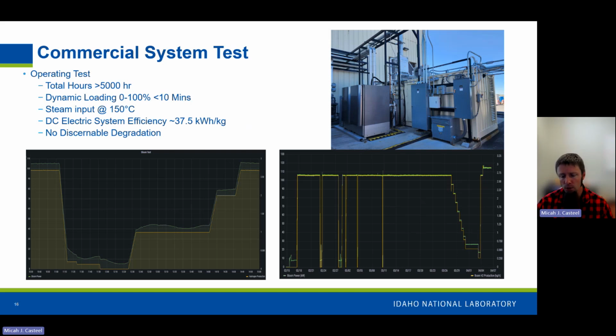The other thing, as I mentioned back in stack testing, is that dynamic loading capabilities of these systems are tremendous. This system has also gone 0 to 100% and back again in a little less than 10 minutes. That's very impressive in terms of how fast these large systems can turn on and off, and that allows them to support the grid in future operations.